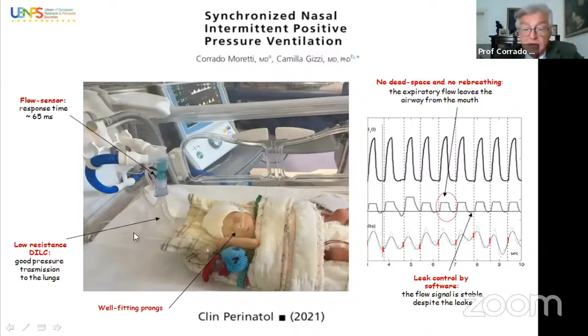Moreover, I underline the fact that the flow sensor detects the inspiratory flow, but never the expiratory flow. If you use a normal flow sensor, you will see that after a few breaths the alarm will beep. You can see here that the flow signal is extremely stable despite the leaks. We obtained this with special software that practically resets the flow to the zero line after every inspiration. So I think we resolved, in a very good way, the problem of variable leaks.